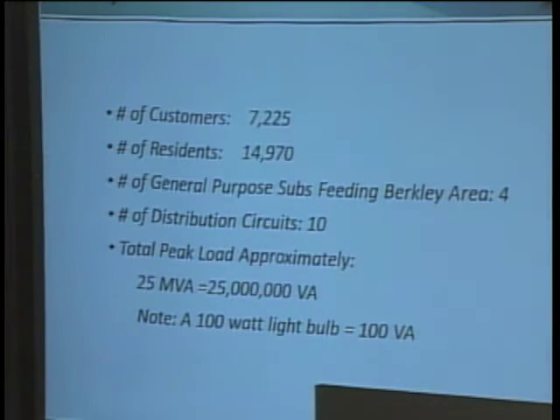The Berkley statistics, we have approximately 7,200 customers from Detroit Edison meters. A number of residents was approximately 15,000 in 2010. General purpose subs are 4, and the number of distribution circuits feeding Berkley 10, with a peak load of approximately 25 MVA, which is equivalent to 25 million volt amperes. And as a reference, a 100 watt light bulb equals 100 volt amperes. So at a peak time period, that would be the same as running 250,000 100 watt bulbs.